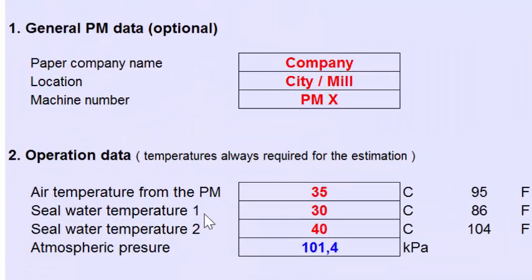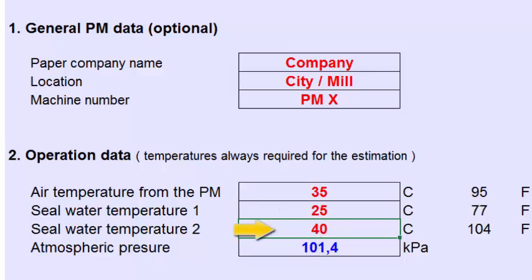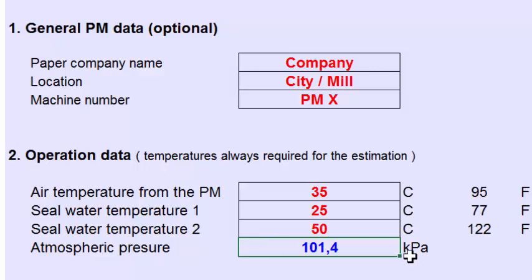The seal water temperature can be given in two different operating conditions. Let's calculate two different situations: one where the seal water temperature is 25 degrees Celsius (77 Fahrenheit), and another where this temperature is very high — let's say 50 degrees Celsius, which equals about 122 Fahrenheit. Let's also suppose that this mill is situated more or less at sea level, so we have normal atmospheric pressure around the vacuum pumps.